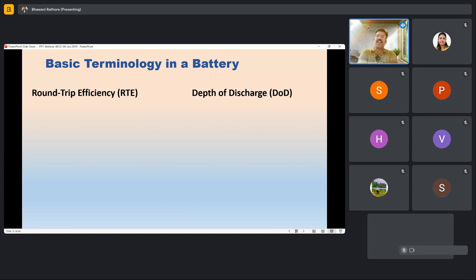If we talk about LFP battery, the depth of discharge is, for example, 90%. Meaning if you discharge up to 90%, its round trip efficiency, its performance, its life cycle will not reduce. But if the OEM has given 85% and you discharge it to 90% or more, above what is given by the OEM, the life and the warranty, which is basically for 10 years, will also be impacted. We cannot go above that.